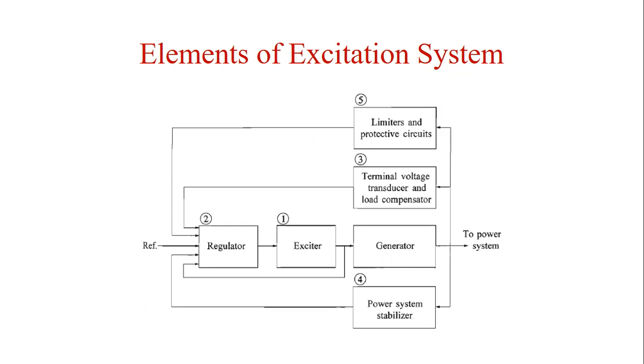The power system stabilizer provides an additional input signal to the regulator to damp power system oscillations. Some commonly used input signals are rotor speed deviation, accelerating power, and frequency deviation. The fifth part of the control circuit is the limiters and protective circuit. This includes a wide array of control and protective functions which ensure that the capability limits of the exciter and the synchronous generator are not exceeded. Commonly used functions include the field current limiter, maximum excitation limiter, terminal voltage limiter, volts-per-hertz regulator and protection, and under-excitation limiter.